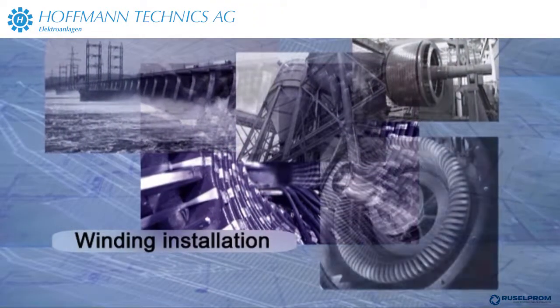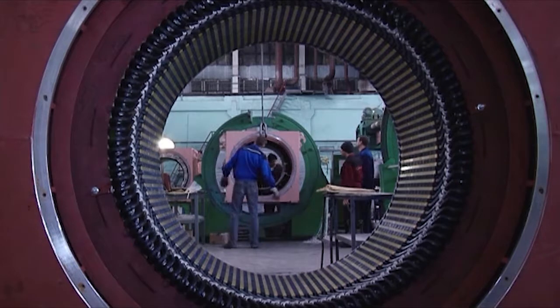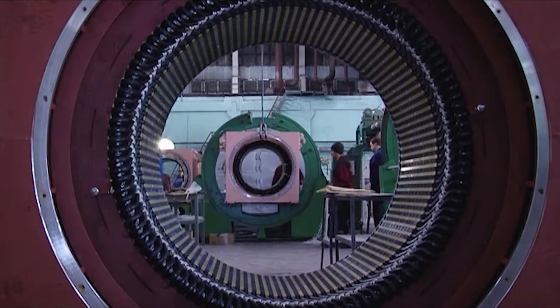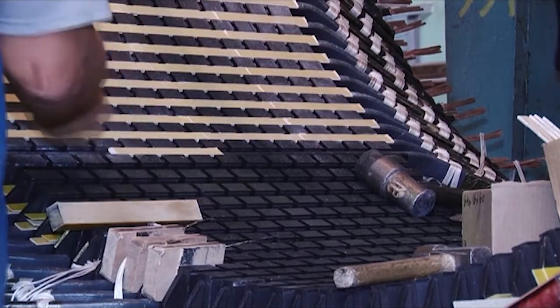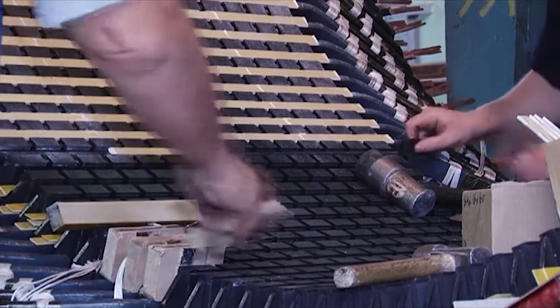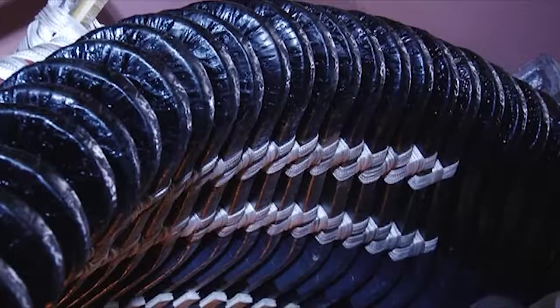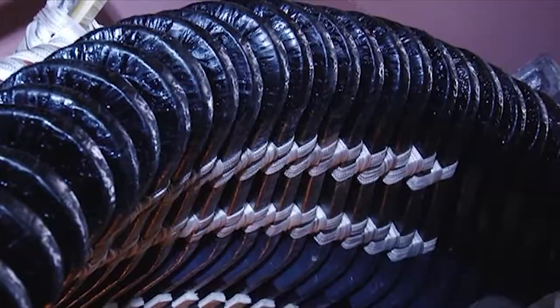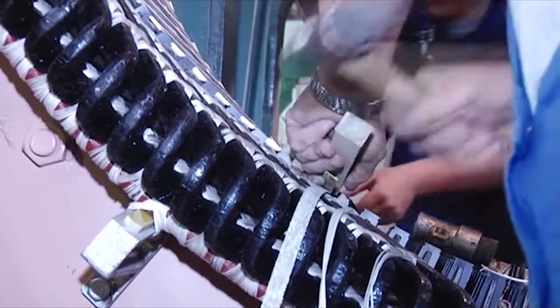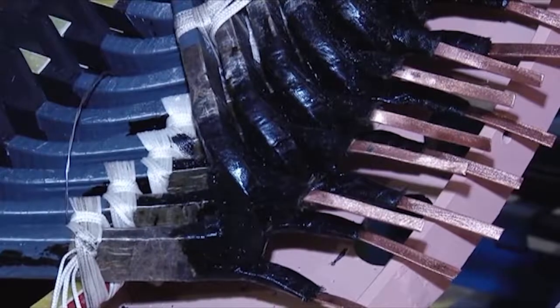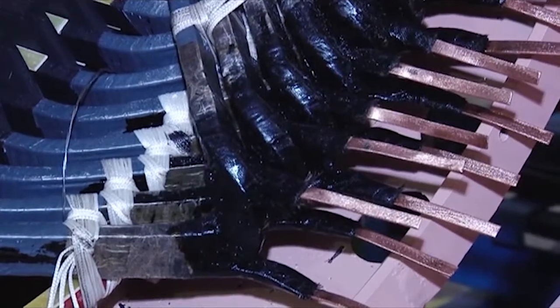The finished winding is installed in longitudinal slots during induction motor stator assembly. Insulating pads are placed at the slot's base between the top and bottom layer coils, as well as under slot wedges used during the winding installation. The coil and winding sections are tied to retaining rings as the winding is installed.